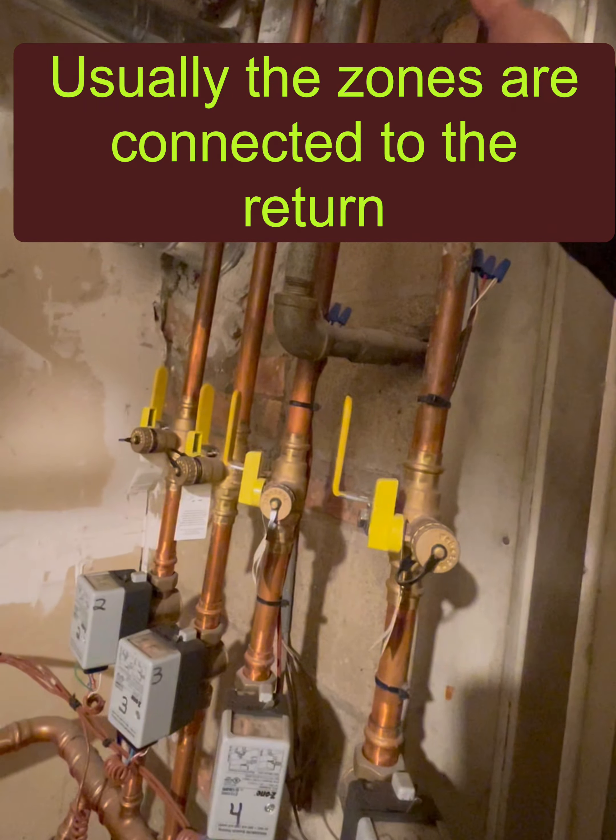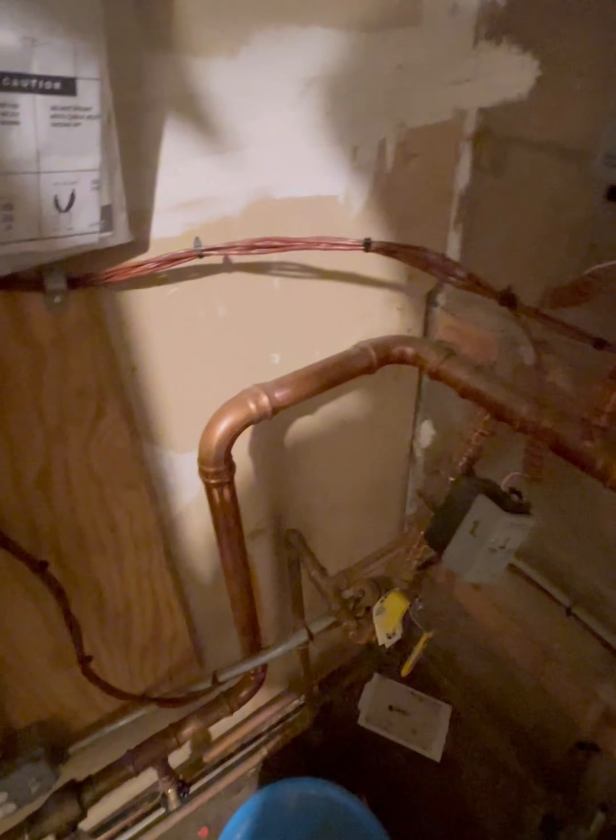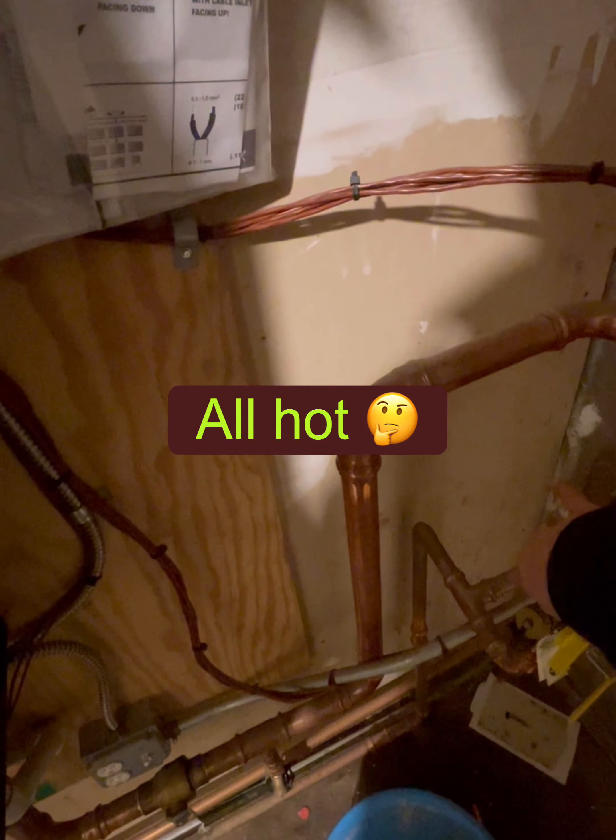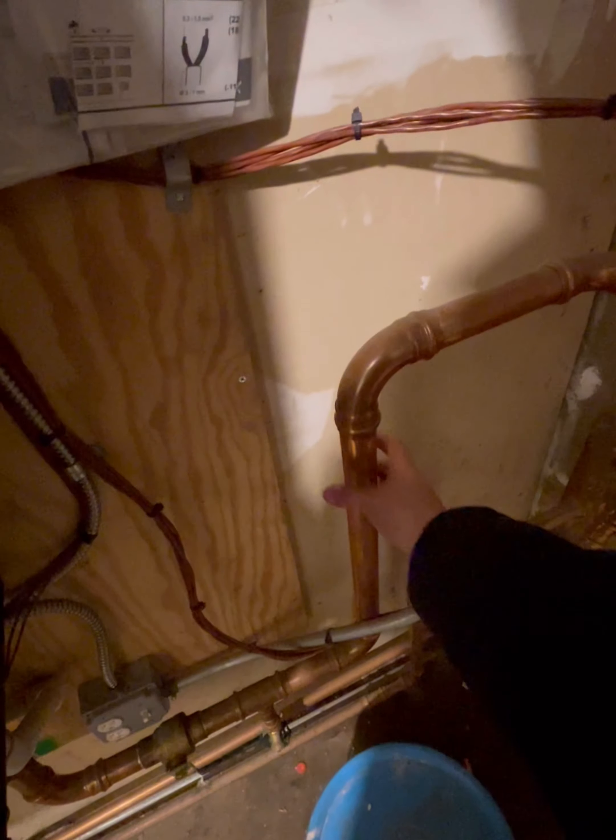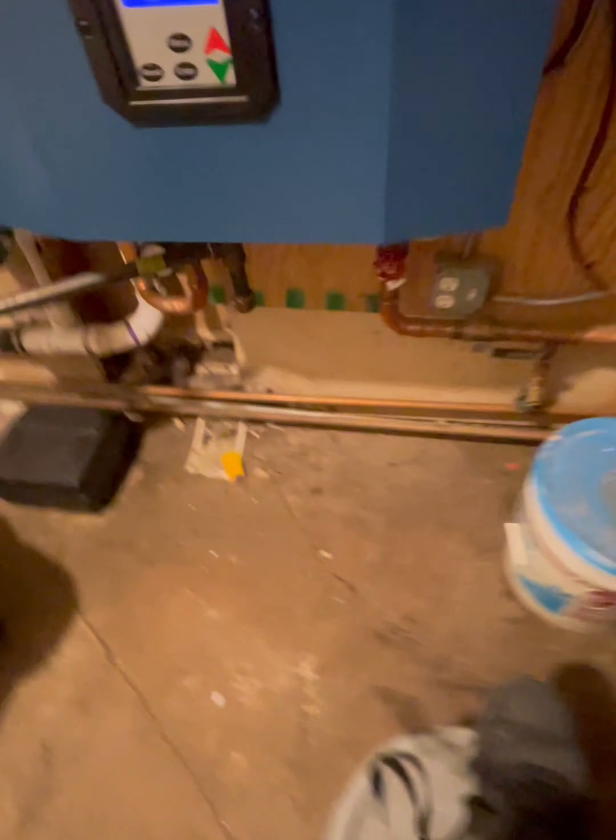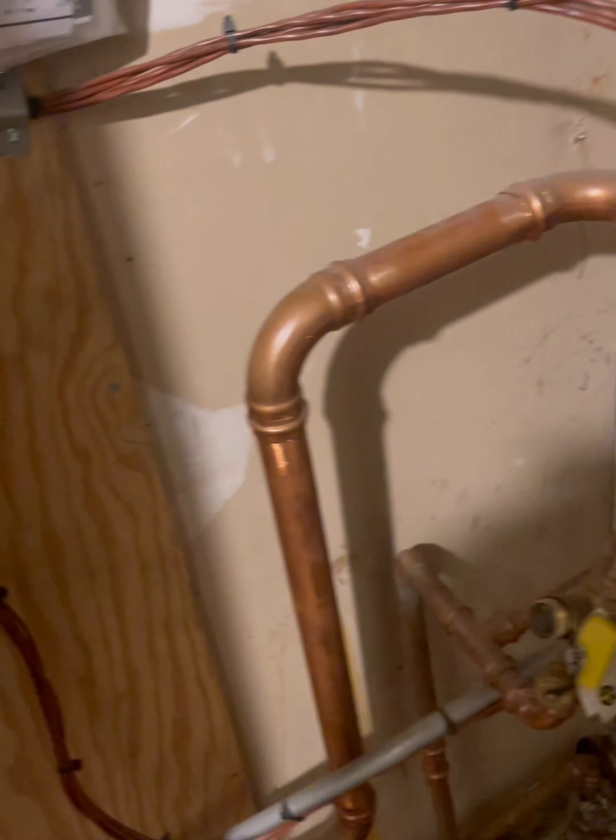Let's check the return here. Hot, hot, hot. They're all hot. This is hot, I don't know why they say it's not hot enough. Hold on one second guys. Alright, so this is where we're at. All these pipes are hot right? One, two, three, four hot to the touch. For some reason when I was bleeding right here it was cold water.